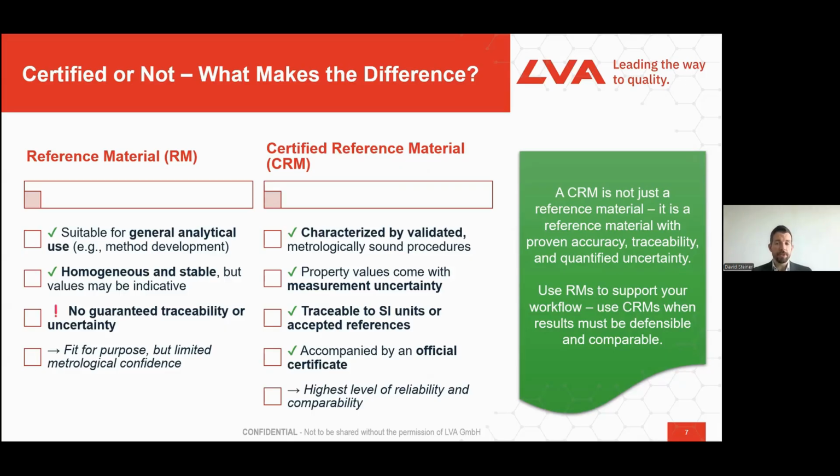So the key message at this point is a CRM is not just a reference material, it is a reference material with proven accuracy, traceability, and a quantified uncertainty. And in practice, this means that while reference materials can support your workflow, a certified reference material is essential when your result must truly be reliable and comparable.